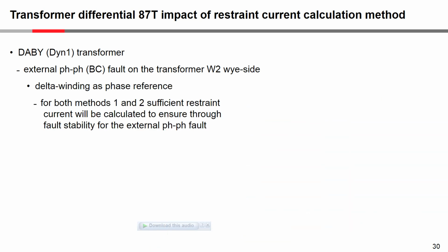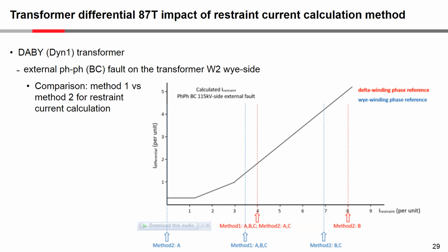But for the delta winding as phase reference, both methods 1 and 2 would calculate sufficient restraint current such that for this external B to C fault, it would ensure stability. Because remember the characteristic, we are in the part of the characteristic where the characteristic is increasing, and so we would get sufficient stability should there be some measurement error, or some small amount of CT saturation. We would have sufficient margin to have stability.